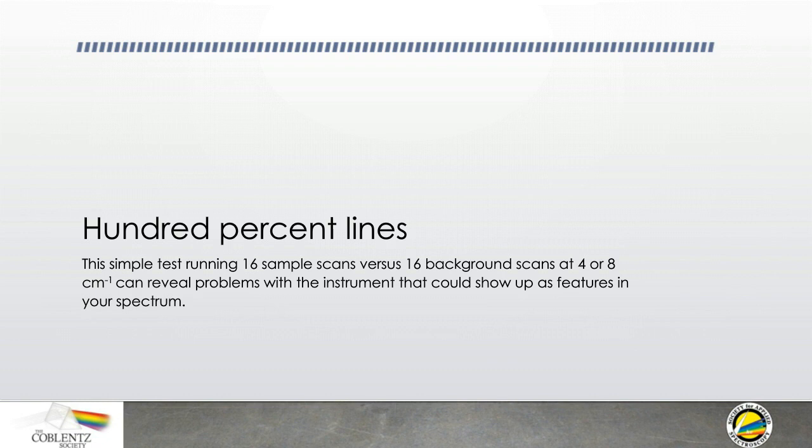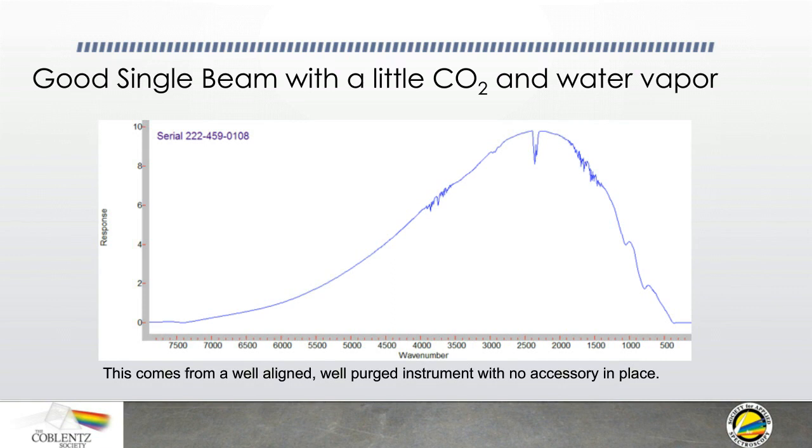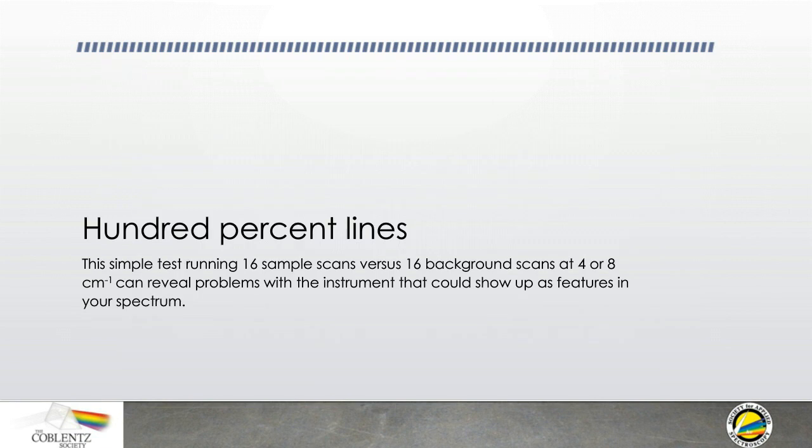So you collect your background, you get a nice single beam, like some of the ones that I showed you early, like this one. Then without changing anything in the spectrometer setup, you go and you collect another spectrum and make that your sample. Again, you take it at four wave numbers with 16 scans. So what you've done is you have matched the resolutions, you've matched the data collect times.